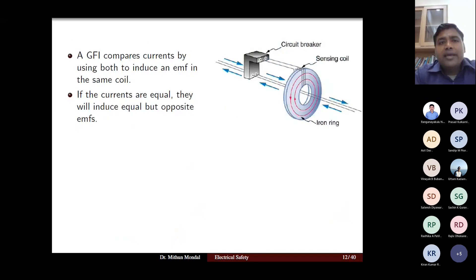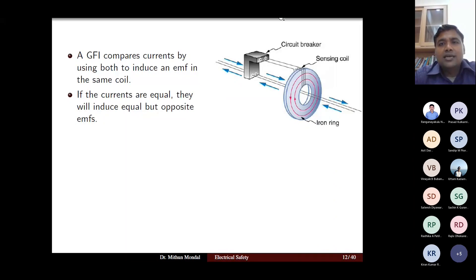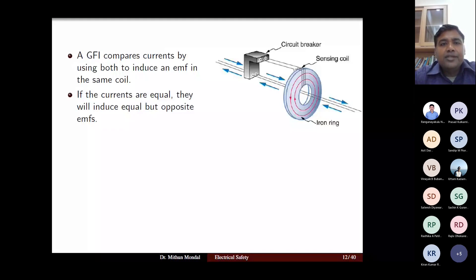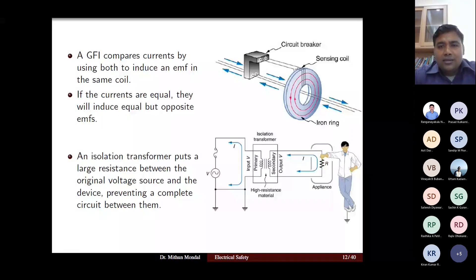The ground fault interrupter compares current in the live wire and neutral wire using the principle of induced EMF in the same coil with a sensing coil and iron ring. A magnetic field is induced in the iron ring. If currents are equal, they induce equal but opposite EMF, which cancel each other. Another important device is the isolation transformer, used especially in substations.